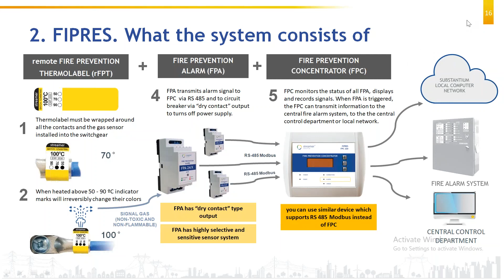standard scenario with fire. Whenever your systems are in place, in a new system, the operating temperature may be around 25 degrees, and it gets heated because of overloads, loose connections, or any other reason. We will take an example of a small cable. I will switch off the video so that we get proper bandwidth. In a particular cabinet, we take an example of a cable. The cable gets heated and cooled, and every time its insulation is deteriorating. A moment comes when insulation gets damaged beyond repair and it starts to rapidly overheat. A time comes when your polymeric insulation starts burning.